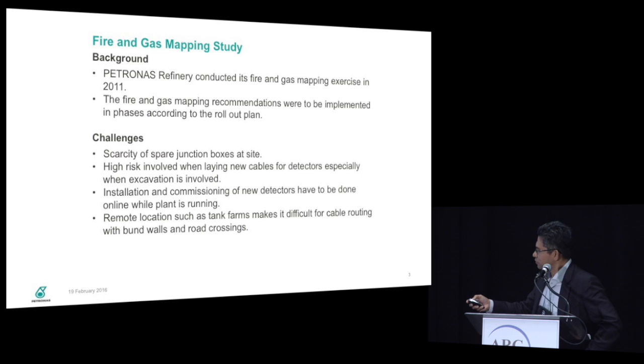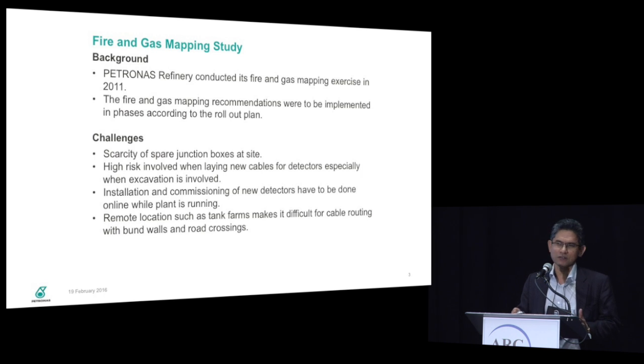The fire and gas mapping recommendations were to be implemented in phases according to the rollout plan. Because the project is quite massive, we staggered it over 5 years. We started installation in 2012 in one of the areas, and in 2013, 14, and so on. In 2013, we were to install the gas detectors in the terminal areas. Terminal areas is where the tank farms are, very big areas.